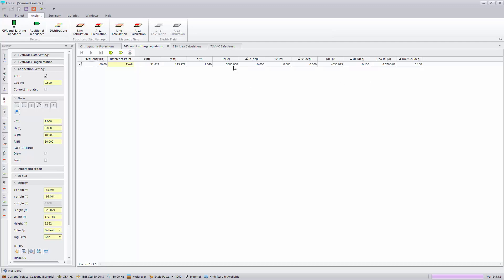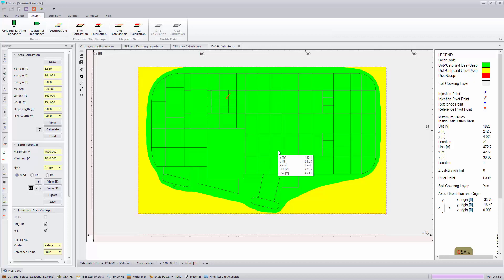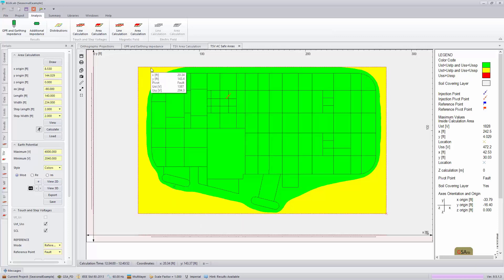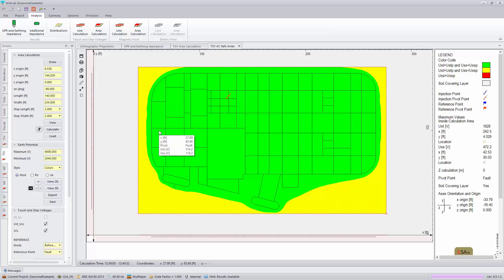Looking at the touch and step voltage criteria plot: green represents locations where touch and step voltages are below compliance limits; yellow areas represent locations where touch voltage exceeds the compliance limit; and red areas would represent failure for both touch and step voltages. Within the outermost loop of the grounding system, we are completely green. This substation in summer is compliant with IEEE Standard 80 for touch and step voltage criteria. But let's see what happens when we change the soil model and look at it when it's colder.